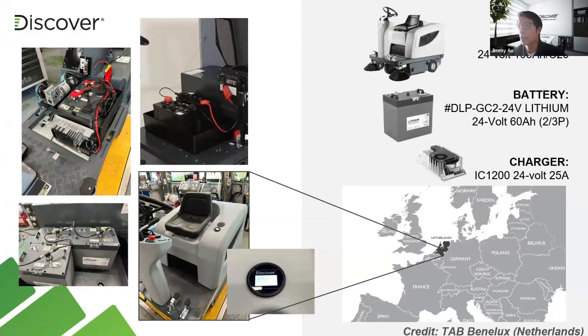If the operator is experienced with battery maintenance and water topping, flooded batteries are a good enough and very economical solution. Otherwise, if you don't want to deal with the maintenance, gel would be more common in Europe, and AGM would then be used for added runtime and capacity. Compared to a gel battery, with AGM you're getting about 15%, if not sometimes 20%, more runtime. So maintenance-free batteries are a good alternative to flooded as well, if that's a benefit to you.